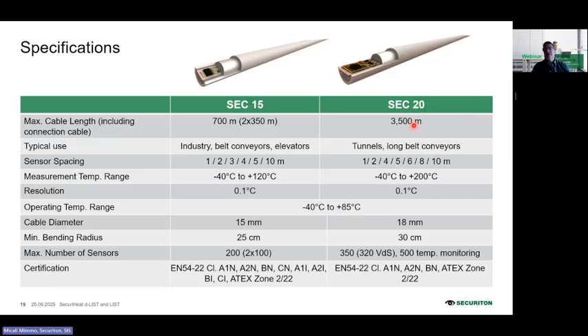Or you use the SEC 20, which can have with one controller up to 3,500 meters. That's very interesting for middle and long tunnels. So you use fewer controllers and you have really the maximum capacity of 3,500 meters or 350 sensors if you use a distance every 10 meters. The measurement temperature range is normally from minus 40 degrees up to 120 with this kind of cable, or 200 degrees if you use the bigger cable. The operating temperature range is normally from minus 40 up to 85 degrees.